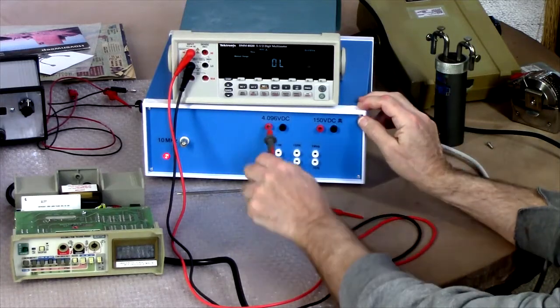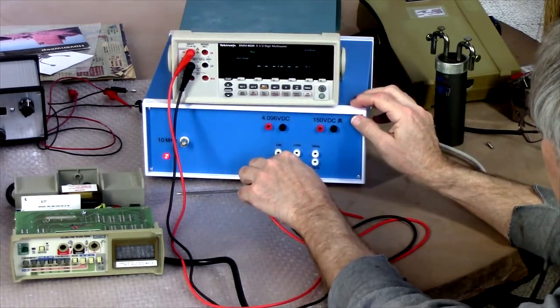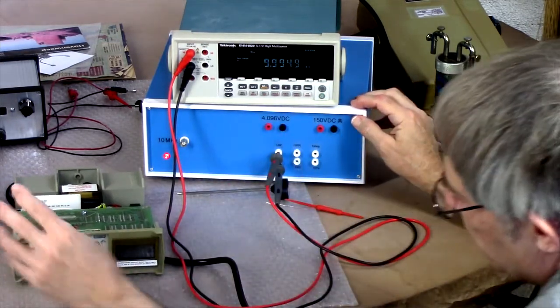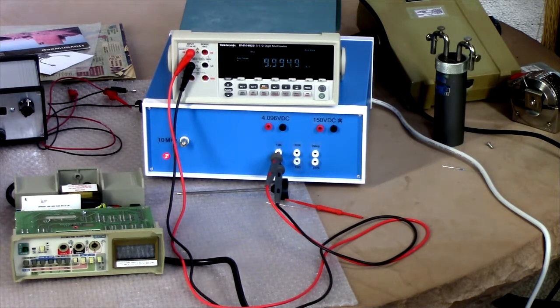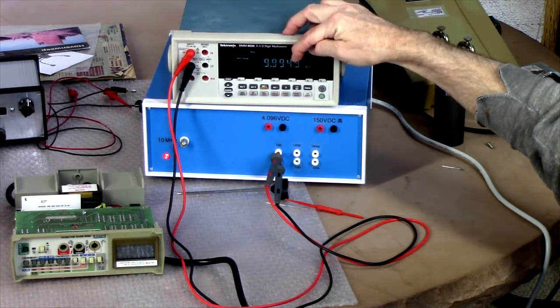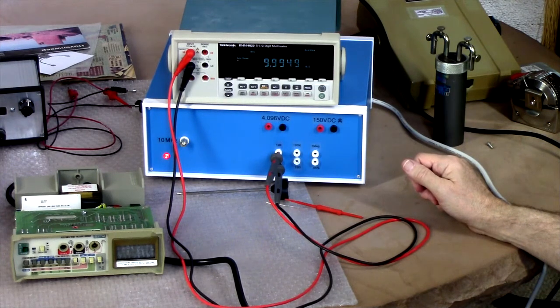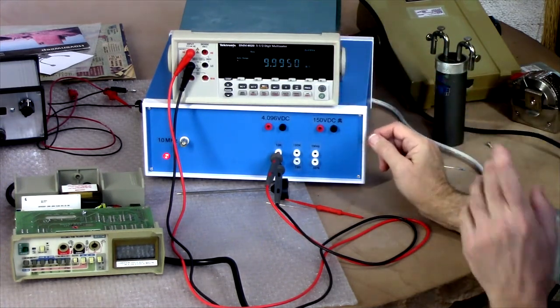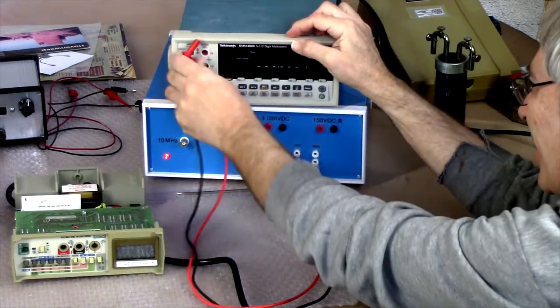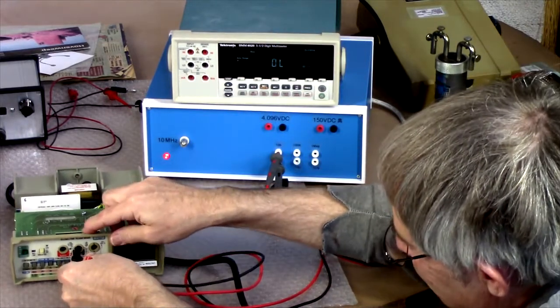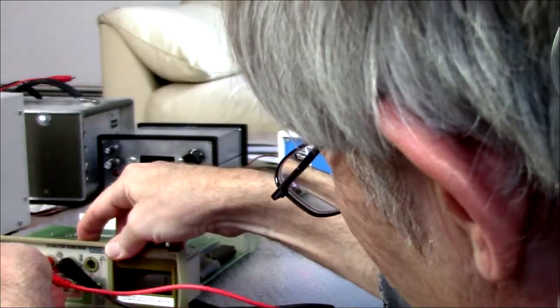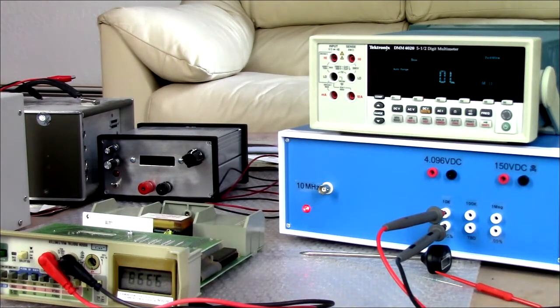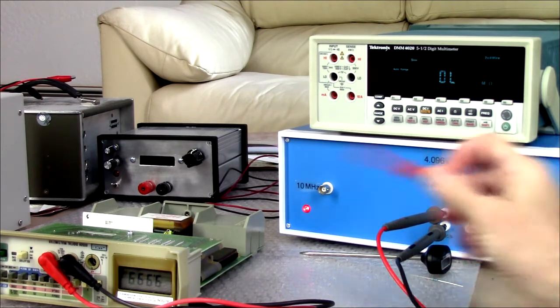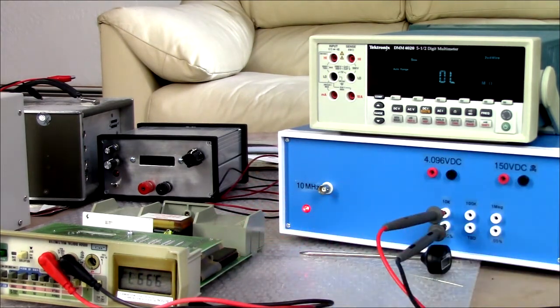This is 10K. I'm going to take off relative. I'll take off relative over here, too. Okay. That's supposed to be 10K, plus or minus 0.005%. Is this 005? Because if it is, it's just barely in spec. Well, we don't know, again, how accurate this thing is. Okay, 99.95. 99.98. There is only one adjustment for resistance on this, and that's on, I think, the 2K range.